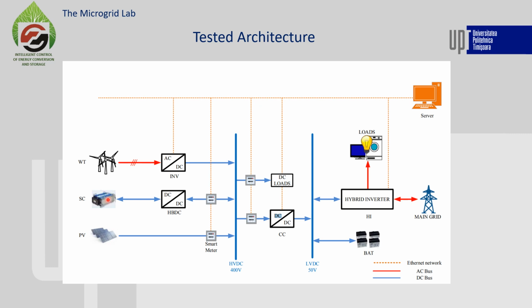The hybrid DC converter uses a nonlinear droop control method for charging and discharging the supercapacitor. The charge controller, together with the hybrid DC-DC converter, is responsible for maintaining the voltage on the high voltage DC bus at around 350 volts DC, based on the amount of energy available from the renewable energy sources.